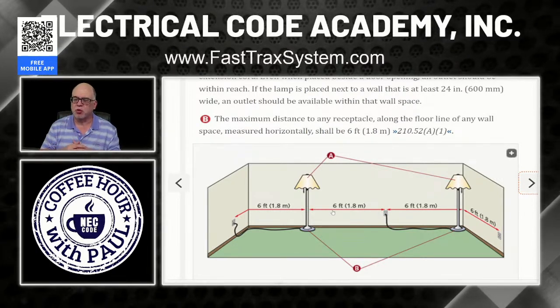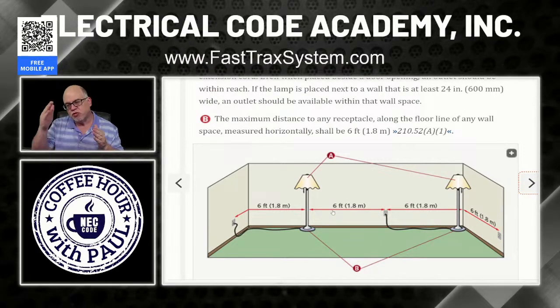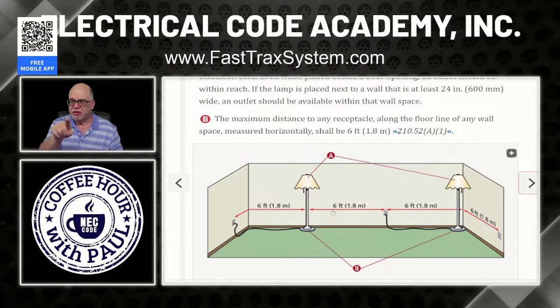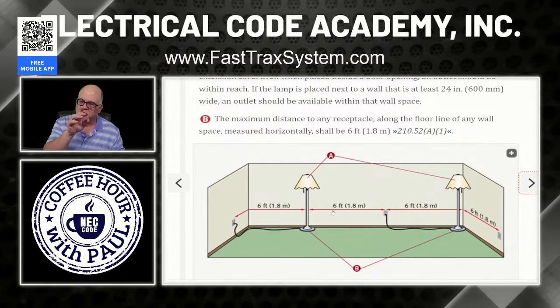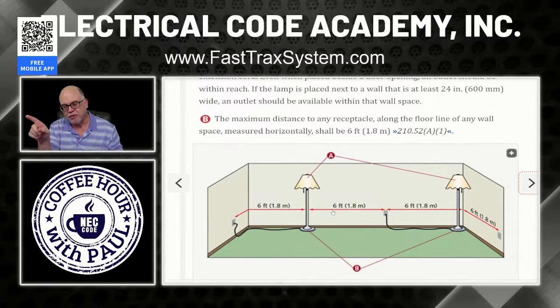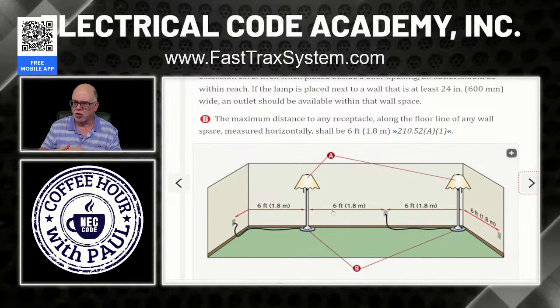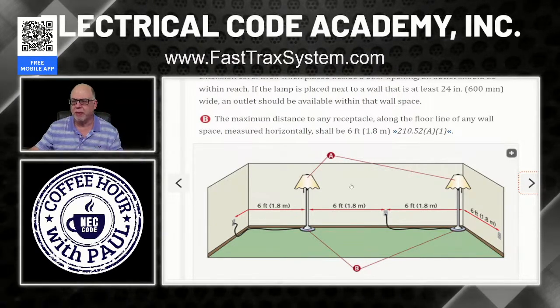The 6 foot, 12 foot rule means 6 feet from an opening or break in the wall line, and you can go a maximum of 12 feet, because if you went right in the middle and touched the wall, you'd be within 6 feet of that receptacle. You move 1 foot to the left or 1 foot to the right, you're still within 6 feet of that receptacle. Or if you move this way, you're within 6 feet of that receptacle. That's what you're trying to do. The standard cord is 6 foot in length, so we have to make sure that we're discouraging the use of extension cords. Thus we call this the 6 foot, 12 foot rule to make it simple to remember.